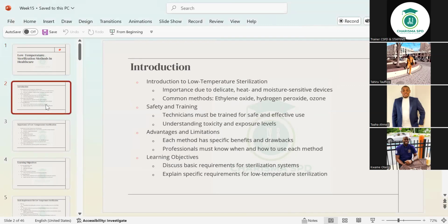Okay, so now the introduction says: introduction to low temperature sterilization, importance due to delicate, heat and moisture sensitive devices. The importance of low temperature sterilization is because there are instruments that are delicate and cannot take heat or moisture. They are sensitive to heat, which means that you can't put them through the 270 degrees, that excessive heat. They can't go through that. And that's where the need for low temperature sterilization comes from. The common methods, as I've told you, are ethylene oxide, hydrogen peroxide, and ozone. Okay. Safety training: technicians must be trained for safe and effective use of these methods, because you can't use something without knowing what to do in case there's a problem or how to stay safe during that process. And that's why we have to train you on that, understanding the toxicity and exposure levels, because all these things, hydrogen, even water can be dangerous.